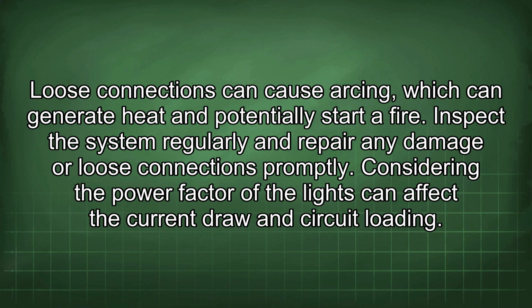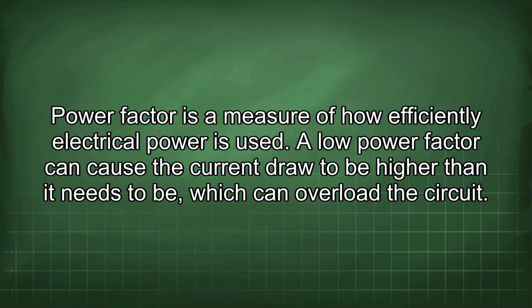Considering the power factor of the lights is important, as it can affect the current draw and circuit loading. Power factor is a measure of how efficiently electrical power is used. A low power factor can cause the current draw to be higher than it needs to be, which can overload the circuit.